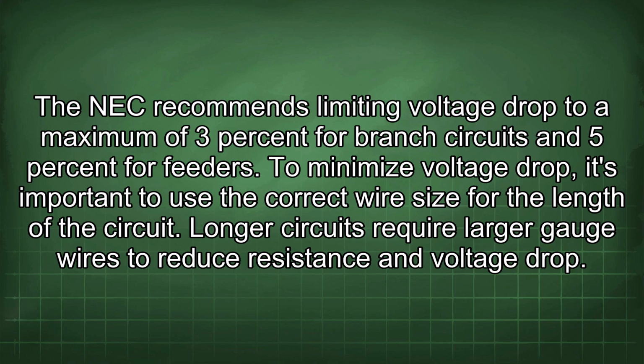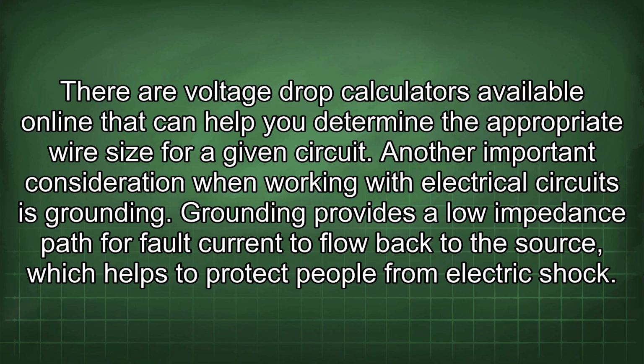To minimize voltage drop, it's important to use the correct wire size for the length of the circuit. Longer circuits require larger gauge wires to reduce resistance and voltage drop. There are voltage drop calculators available online that can help you determine the appropriate wire size for a given circuit.